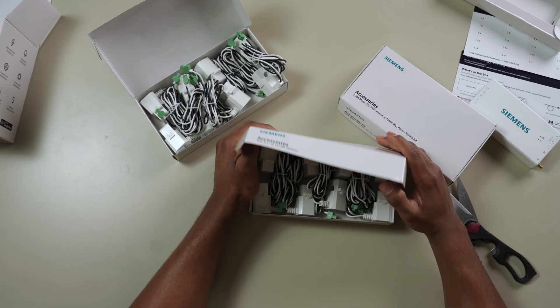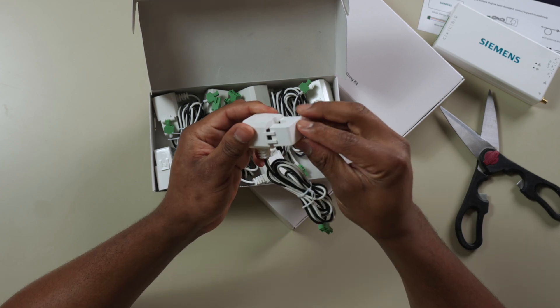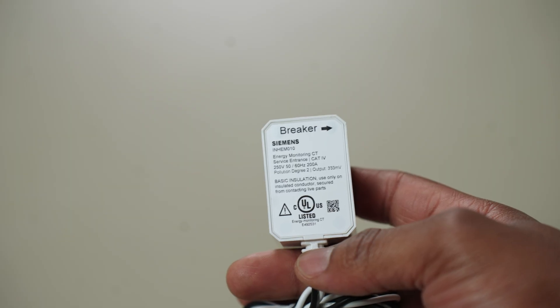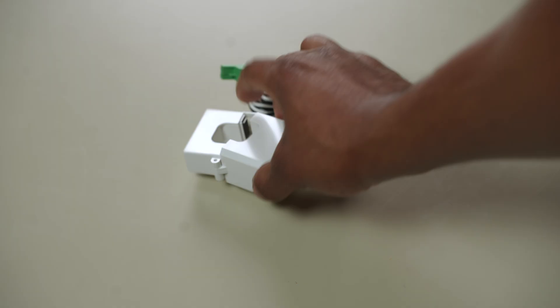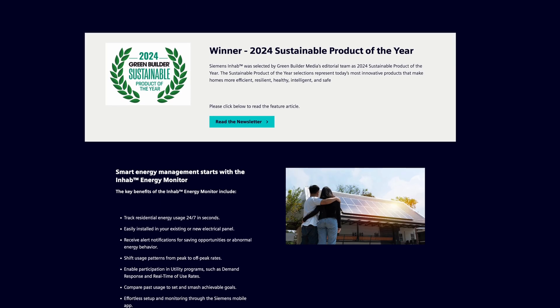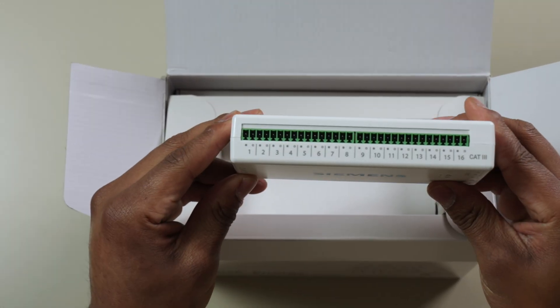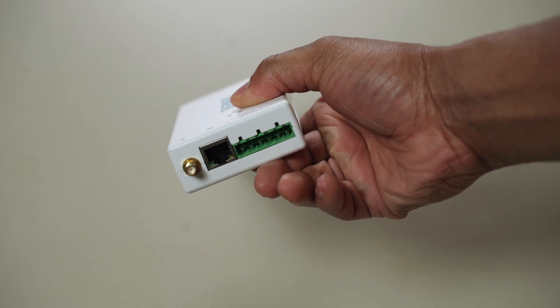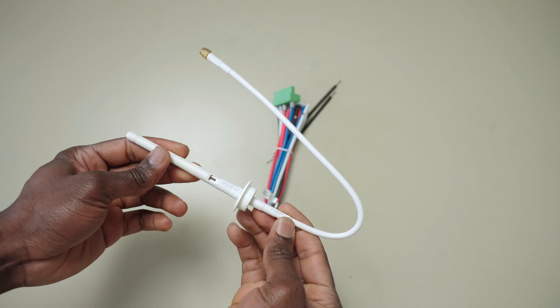Let's talk about what's inside the box. First, we have 16 branch circuit clamps, each rated for 50 amps. They snap onto individual breakers to track energy usage for different zones or appliances, like my basement suite or my kitchen. There are also two large 200 amp CT clamps for the main power line — this monitors total energy going into the home, and one can also track solar production. The main monitoring unit ties everything together, with ports for all 16 branch CT circuits, a terminal block for power, an ethernet port, and a coaxial connector for the included Wi-Fi antenna. They also include splice wires, a wiring harness, and a circuit label to make installation cleaner and easier.